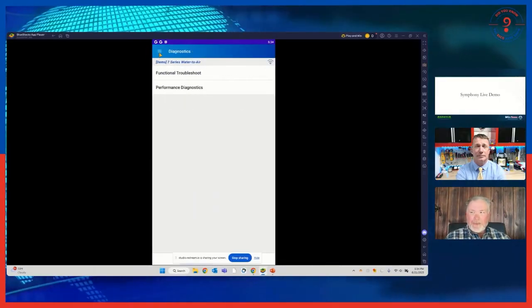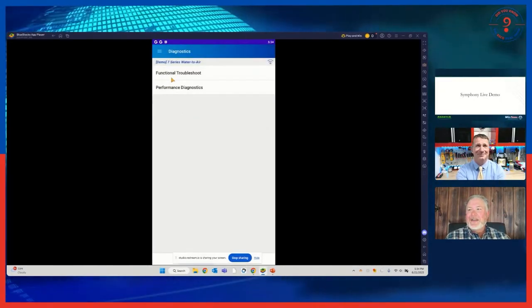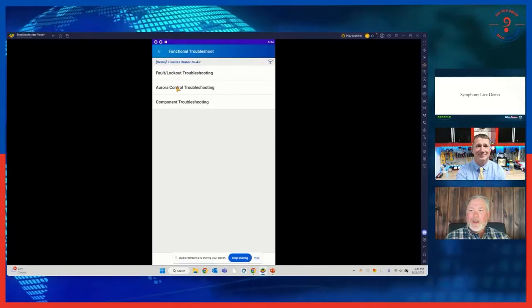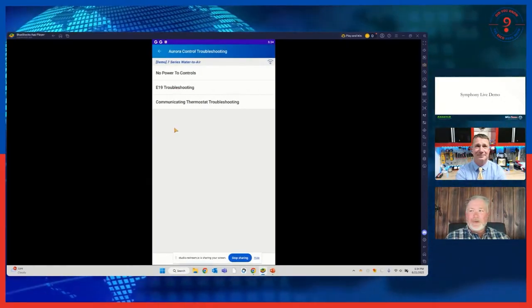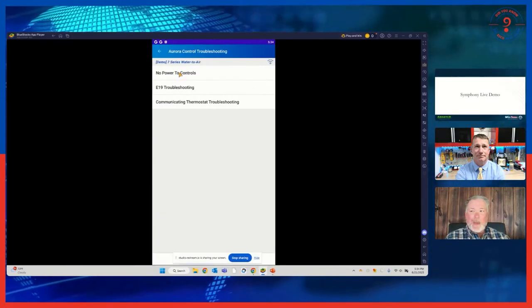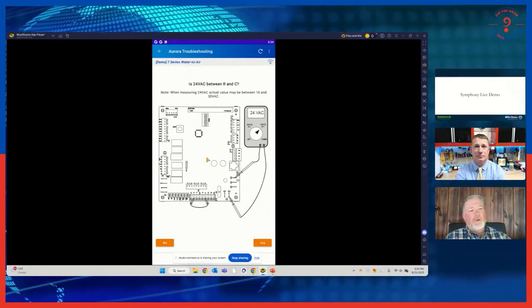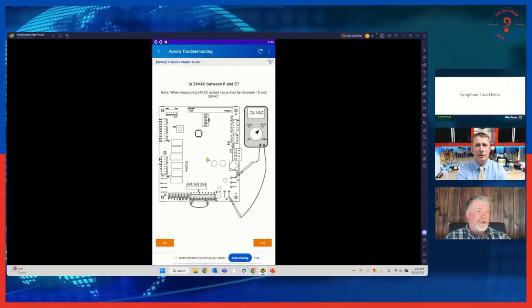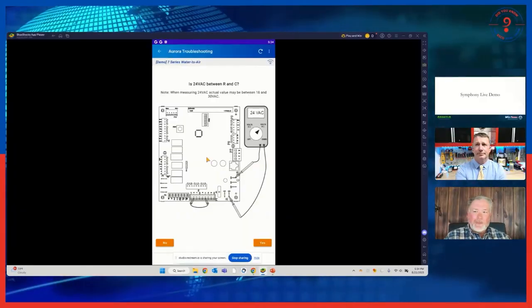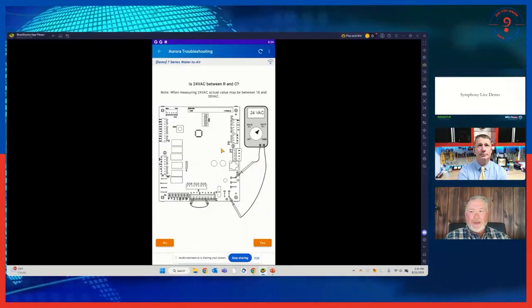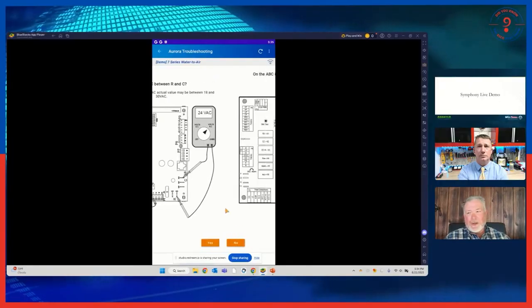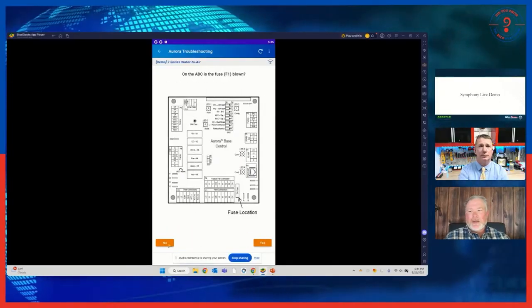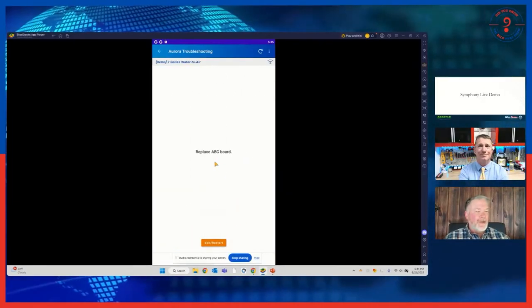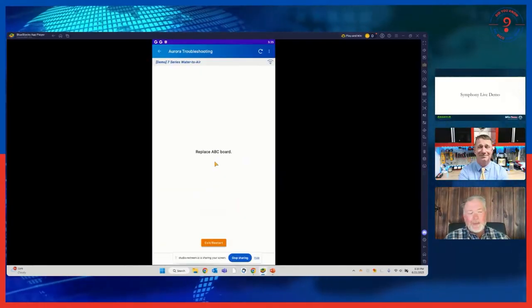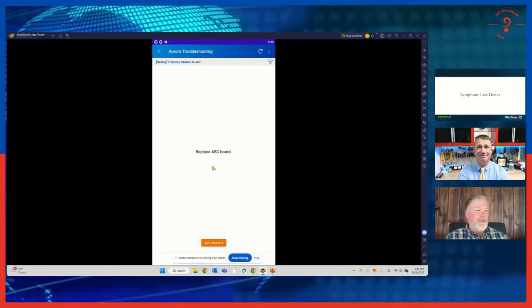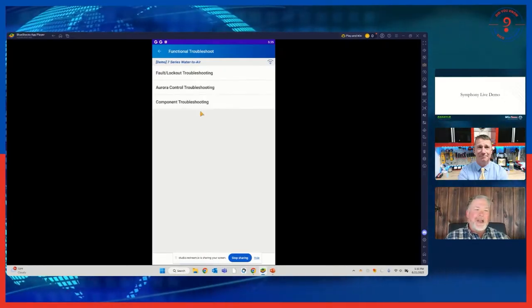Even better, on the diagnostic side, if we go into functional troubleshooting, I can go into the controls and do troubleshooting. Let's try no power to controls - this will ask you questions and guide you through. So we're diagnosing a control board: is there 24 volts between R and C? Let's say there is. Is the fuse blown? Let's say it's not. Well, if I don't have power in my control board, but I have power to it and my fuse isn't blown, then replace the ABC board.